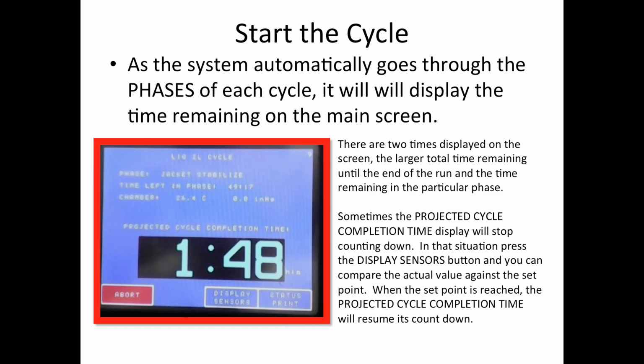Sometimes the projected cycle completion time will stop counting down, and you'll be wondering what the system is doing. At that point, you should press the Display Sensors button. By pressing the Display Sensors button, you will see what's actually happening, and you can see if it's counting down or if it's coming up, what the autoclave is doing, what it is programmed to do, and how close the two are matching.